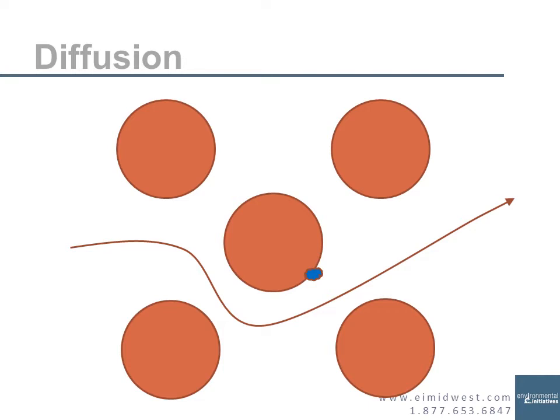So in this case, diffusion happens for viral particles, submicron particles from mold, other things. One thought that people will often say is that filters can only take particles down to a certain size. Not true. Really small particles simply get caught through other methods, like diffusion.